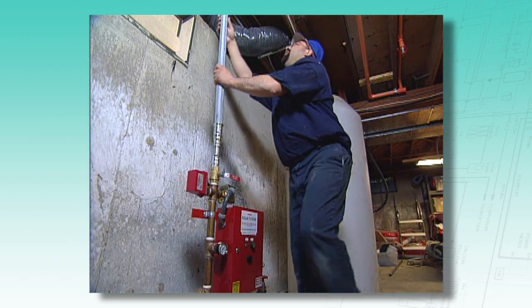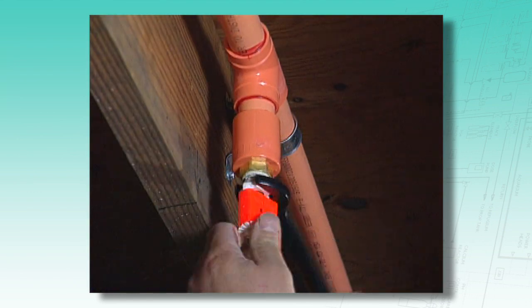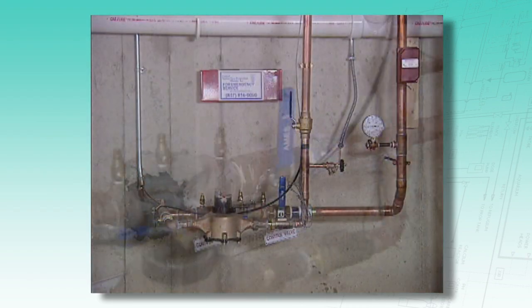Water utilities are pretty familiar with the traditional commercial and industrial fire connections, which are always a separate and distinct pipe from the domestic water supply to a building. The NFPA 13-D fire standard allows designers to utilize just a single line that supplies both fire and domestic flow.